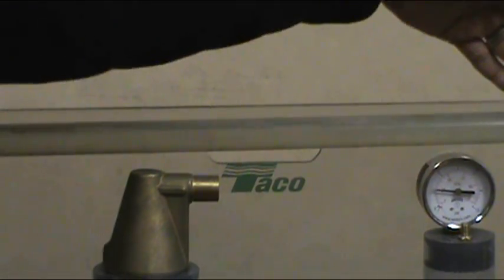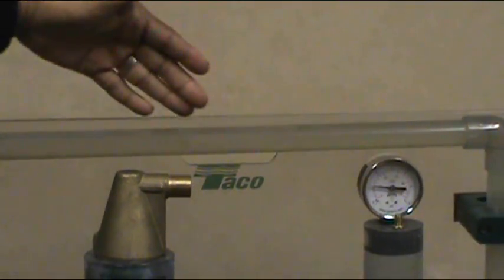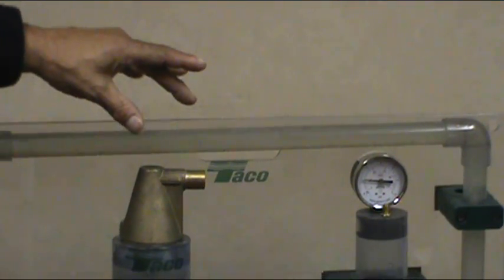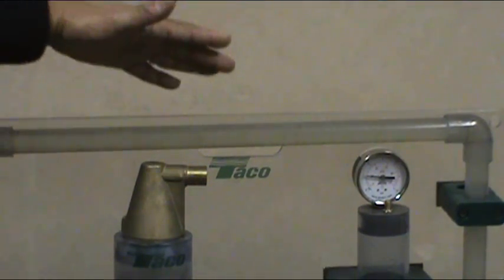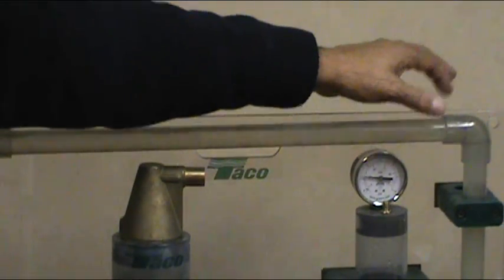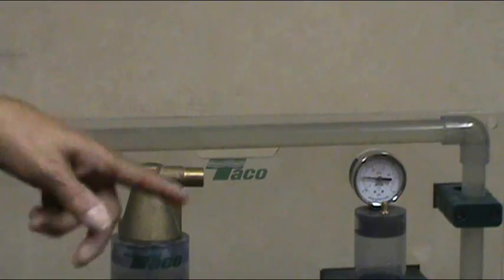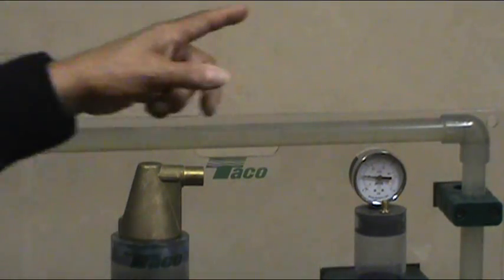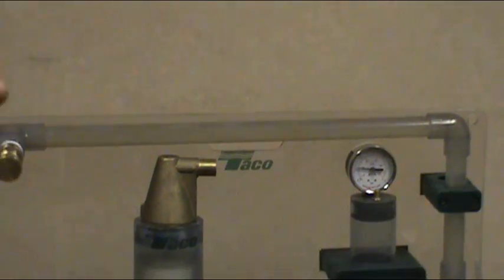Air wants to rise, but because it's moving and the turbulence happens at this point, it takes distance for that air to get to the top of the pipe so it can enter the air scoop on top. By putting the air scoop right next to the elbow, the tendency is for the air to blow right through, continue through the system, come back around again, and never go away.